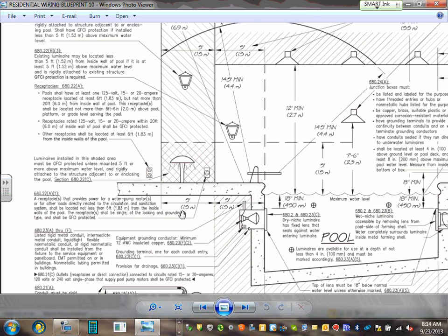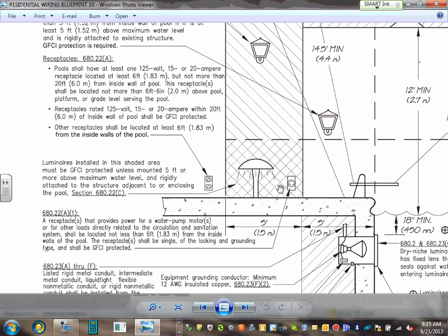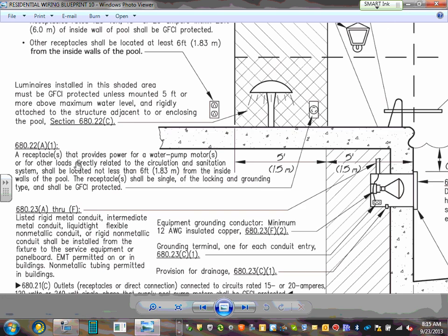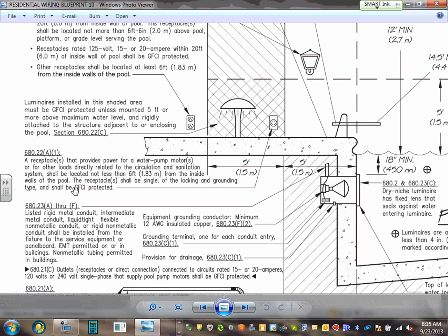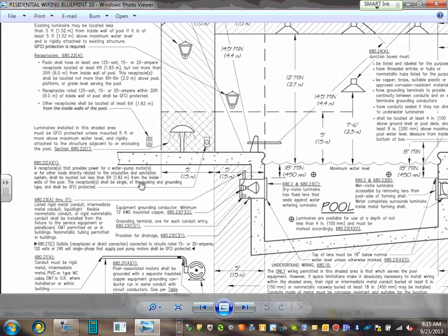Look at this one. There's a certain receptacle that can enter that 5-foot area here. For example, a receptacle that provides power for a water pump. If there is a receptacle that provides power for a water pump or other equipment directly related to the circulation system, it shall be located at least 6 feet from the inside of the pool. The receptacle shall be single, locking and grounding, and shall be GFCI. So if you plug in the circulating pump, it has to be not closer than 6 feet, GFCI, locking type. So that's just for your pump.